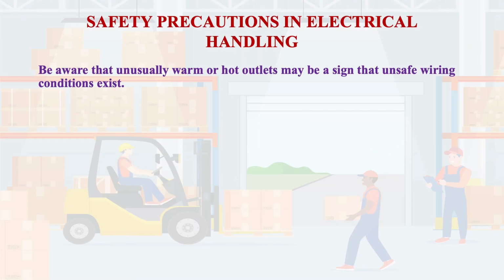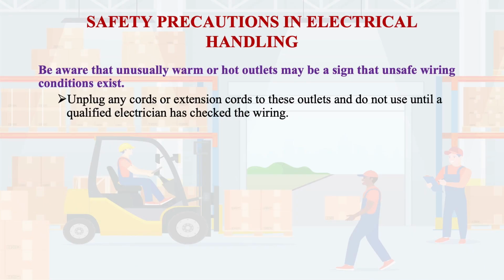Unusually warm or hot outlets may be a sign that unsafe wiring conditions exist. This is very important. If your wire is getting heated up, or hot outlets are there, this means it is an unsafe condition and the wiring can fail. In this case, unplug the cord or extension cords from these outlets and do not use them until a qualified electrician has checked the wiring.